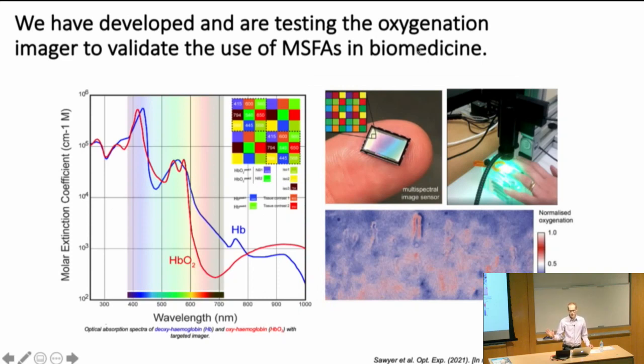oxygenation. And so again, that's pretty much always the first step that everyone always does in spectral imaging, is you see if you can get the hemoglobin, deoxyhemoglobin, and figure out how much oxygen's in it. So we built, we plugged in the data into our algorithm. We had it select the spectral filter array, patterned that onto a sensor, stuck it in a camera, took some images. And so these, again, are quite preliminary, but essentially it's showing that the capillaries in your finger have a lot more oxygen than the surrounding tissue, which is qualitatively what we would expect.